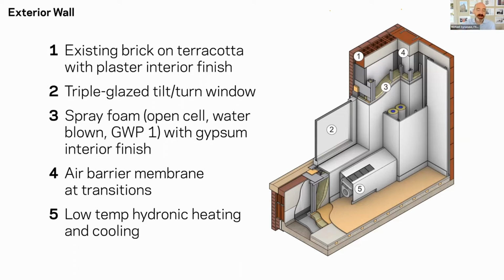It's critical to tape all of these joints onto the ceiling and onto the floor. On the floor, we built a mini concrete slab to have a smooth surface to install that membrane flashing. The exterior wall is where this all comes together with the window, which we supported from steel studs with metal plates cantilevering off, because we could not drill into those terracotta blocks—they would not support the weight of the window and the required wind loads. Also, the fan coil units that Jeff will get into later are below the windows, with the mechanical piping running up along the exterior facade.